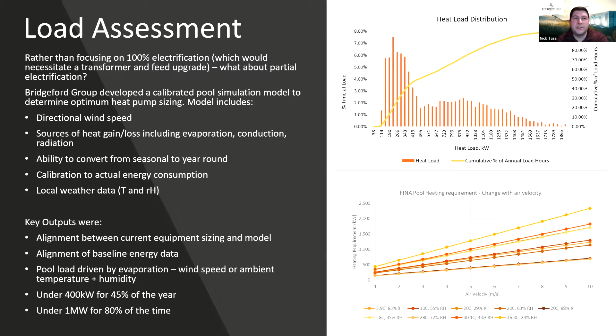Given the pool load was driven by evaporation, wind speed, ambient temperature and humidity, this model produced some interesting results. What we can see with that heat load distribution is that 45% of the year the load is under 400 kilowatts, and under a megawatt for 80% of the year. So what we actually looked at was partial electrification to provide the best bang for buck from an emissions reduction opportunity.